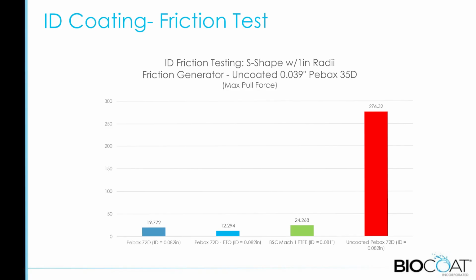But for instance, in one test we did, where we have an S-shaped curve and we're running a tubing through there, we were getting with an uncoated Pebax about 270 grams of force, and it was really tough to push that through. In comparison, a Teflon lined device of that same diameter would be down at around that 25 gram level. So like a 90% reduction from there.